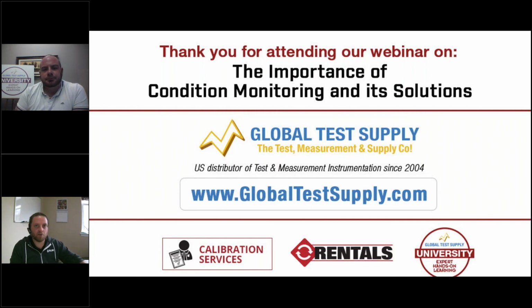That's a good question. Generally speaking, your ultrasonic camera and your regular thermal imaging camera are not going to pick up an SF6 leak. Potentially your acoustic imaging camera could, if the leak is big enough. But if it's that big and getting picked up, it probably needs attention right away. The best tool to use would be one of our gas finding cameras.